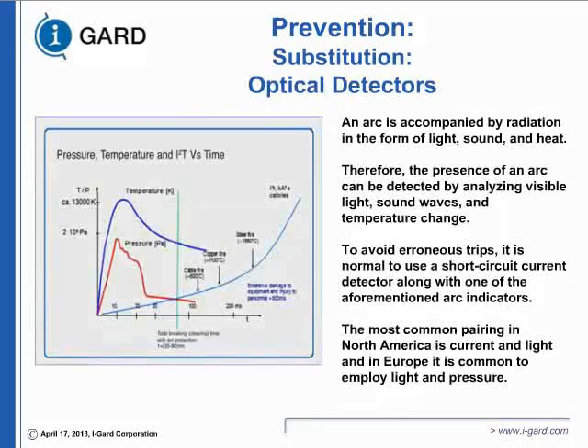The fastest device you can get is optical. Whenever there is an arc flash, it is accompanied by sound and light. Sound travels at 340 meters per second. Light travels 300 million meters per second. So the first thing you'll always see in the flash is the light, then you hear the sound. That technology is very effectively being employed by manufacturers to reduce the incident energy and cut down the time. Basically, the thrust of all the zone selective interlocking, optical detection, or current limiting fuses is to cut down the opening time.